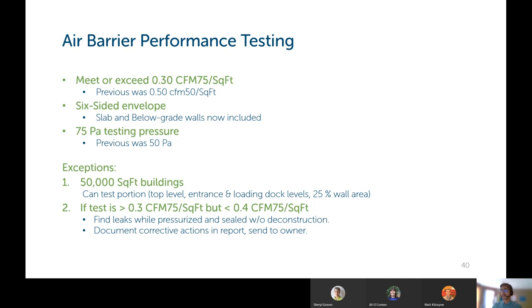So if you're doing performance testing of the air barrier, you need to meet or exceed 0.30 CFM 75 per square foot. The previous version of the code was 0.5 CFM 50 per square foot. So the changes to this are the lower air infiltration rate, the fact that the test now needs to be done at 75 pascals of depressurization instead of 50, and it is a six-sided surface area calculation as opposed to five sides in the previous code. So now the slab and below grade walls will be included in the calculation of the surface area.